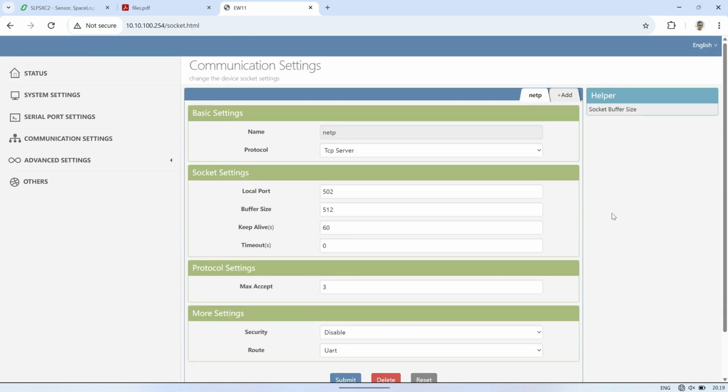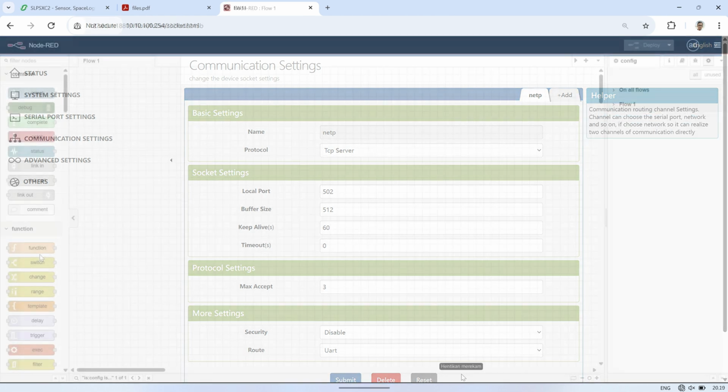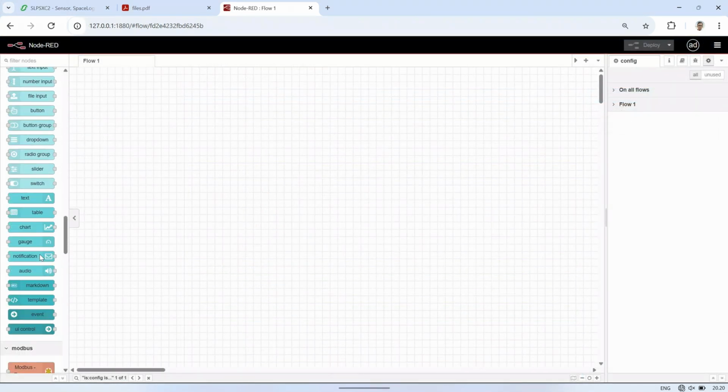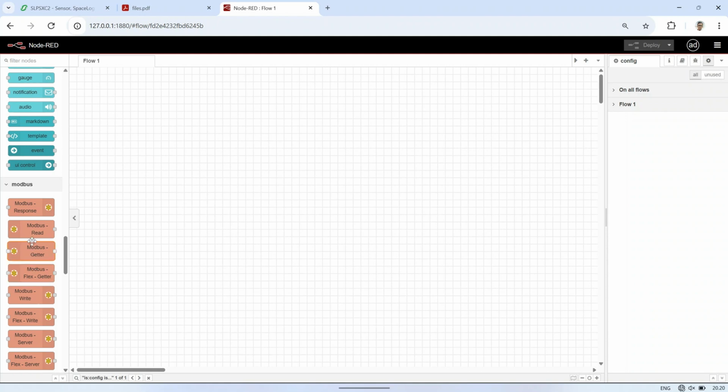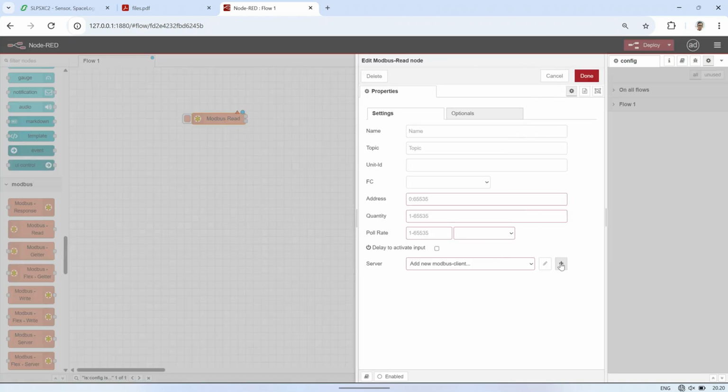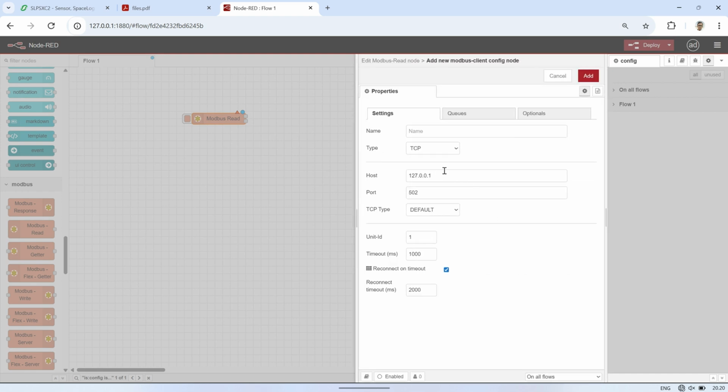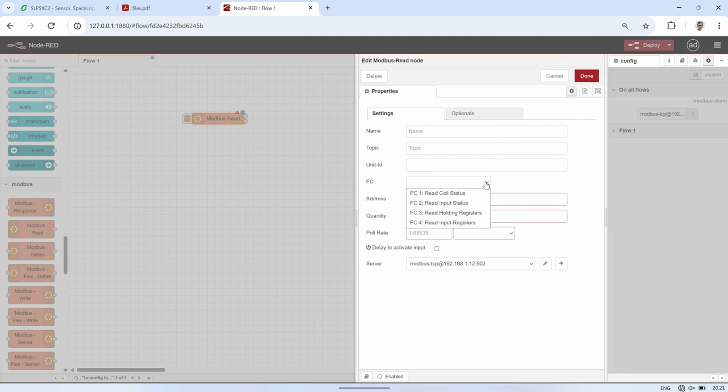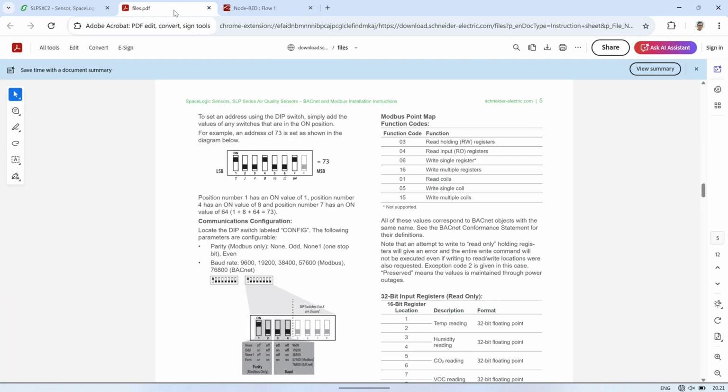To read values from the Modbus device, I'm using Node-RED again. In Node-RED, we'll use the Modbus node to retrieve the data. In the Modbus node configuration, add a new server, enter the IP address that matches the adapter's configured IP, and set the correct port number. Make sure to select RTU buffered mode instead of TCP native. This is because the adapter is essentially bridging Modbus RTU communication over TCP, so the data is transmitted in the same frame format as RS485 RTU.